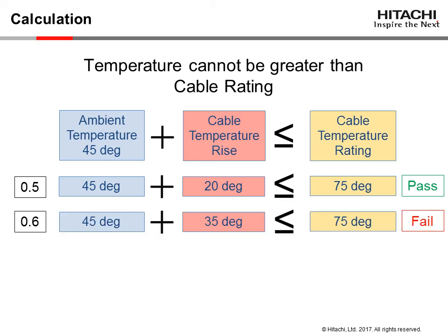Next, 0.6 amps are applied to the same cable, resulting in a 35 degree temperature rise. This, plus the 45 degree ambient temperature, exceeds the 75 degree maximum operating temperature, and results in a failure.